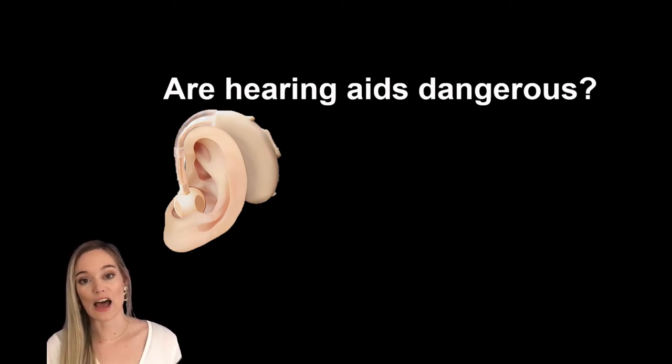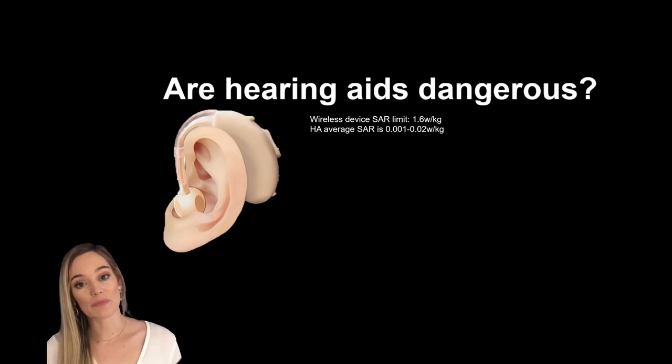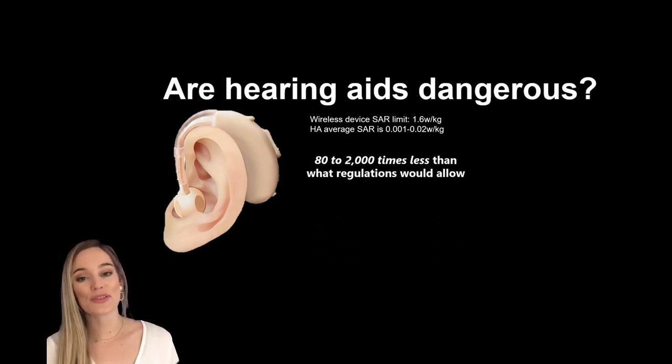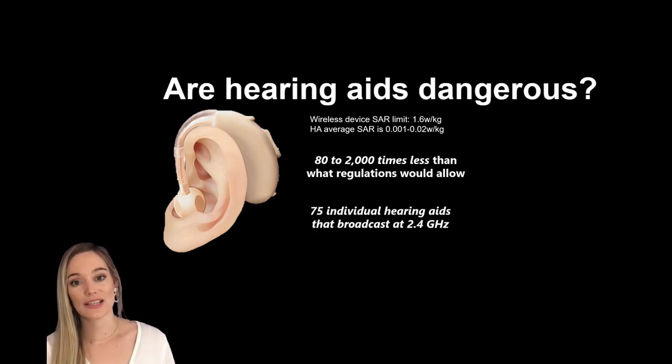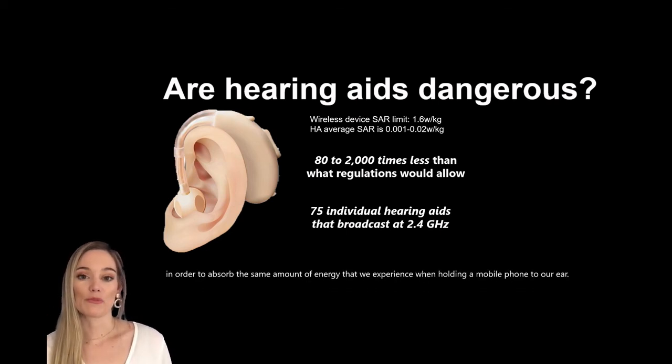The regulations allow for 1.6 watts per kilogram and your average hearing aid SAR value is between 0.001 to 0.02 which is 80 to 2,000 times less than what regulations allow. To give you even more perspective you would need to wear 75 hearing aids on one ear for the SAR value to just reach the maximum allowance for radiation for it to be considered dangerous.